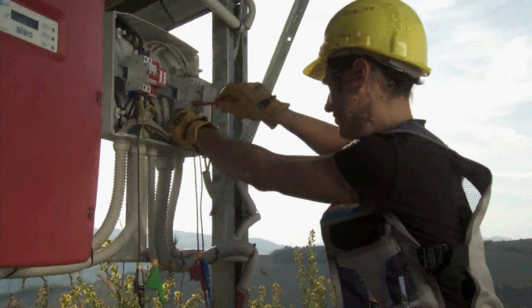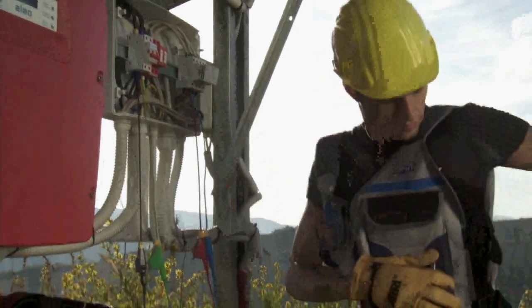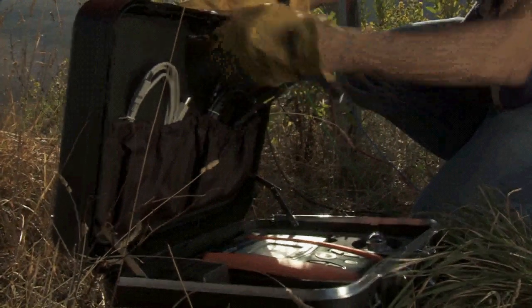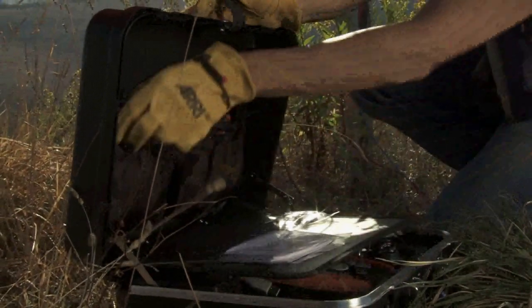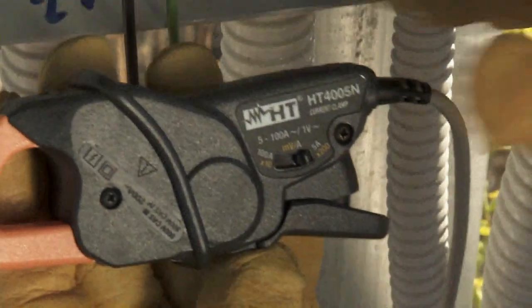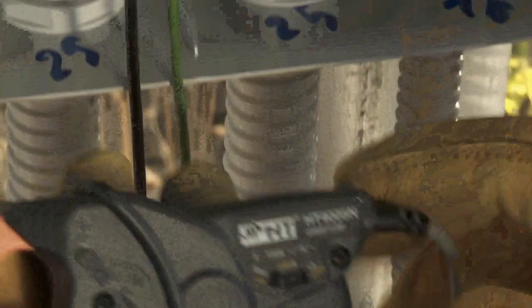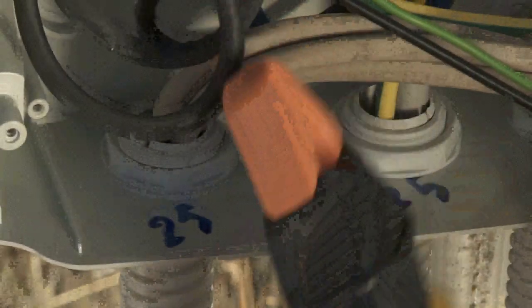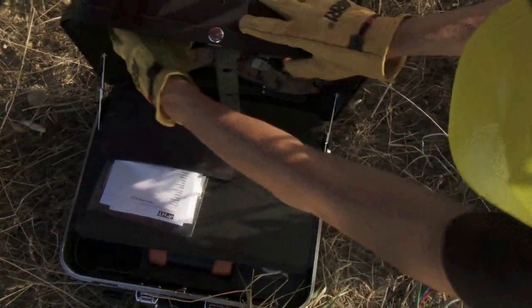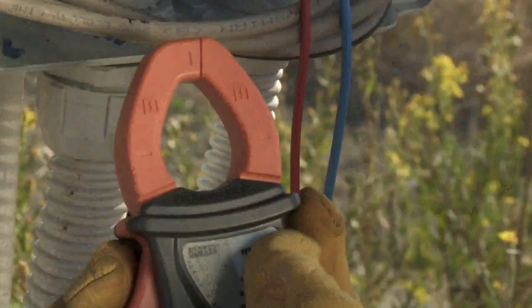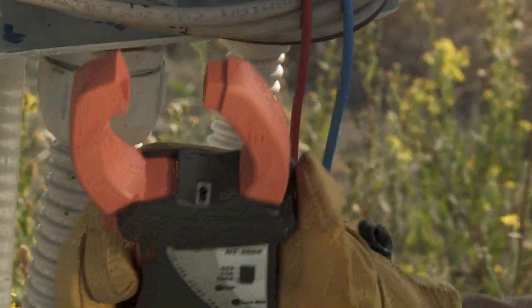Amperometric connections are made by means of appropriate AC and DC clamp transducers. For each amperometric transducer, it is important to select the correct capacity and to respect the indicated plug-in direction. In case of a verification on a three-phase system, 3 AC clamp transducers are needed. After selecting the correct full scale, the DC amperometric transducer is positioned on the positive input pole of the inverter, respecting the direction indicated on the clamp itself.